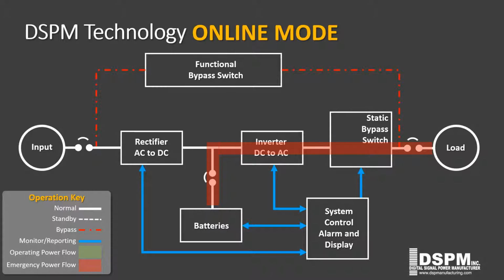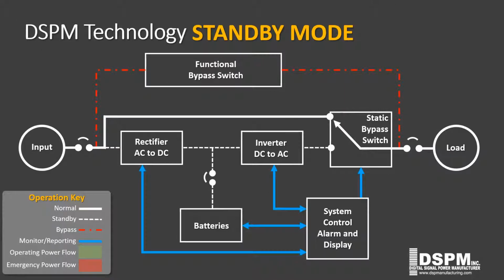At first glance, DSPM's standby inverters look very similar to our online inverters. The only difference is how power flows through DSPM's standby inverters. Basically, during operation, illustrated by the green line, the delivery of power to your load is directly from the utility provider to your load, controlled by the solid-state static bypass switch. In the event of a power failure, illustrated by the red line, the static bypass switch quickly and seamlessly transfers to the standby batteries in 16 milliseconds or faster when needed.